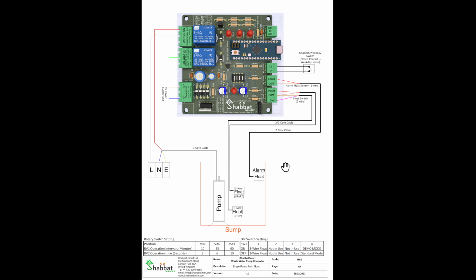So when we commission the system and we want to check the Shabbat operation, we don't have to wait for the time interval between 10 and 60 minutes to see the operation and test it. We put it into commissioning mode, and then it will operate every 20 seconds. It will activate the pump, and then when we raise and drop the float, we can see the operation over Shabbat.